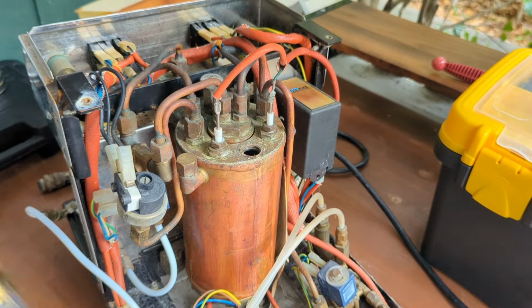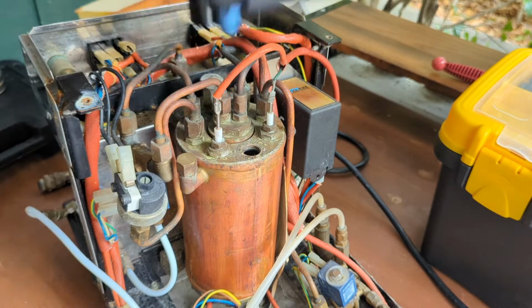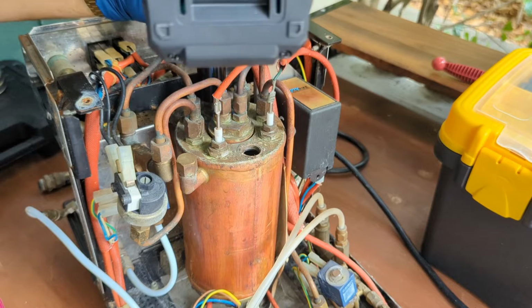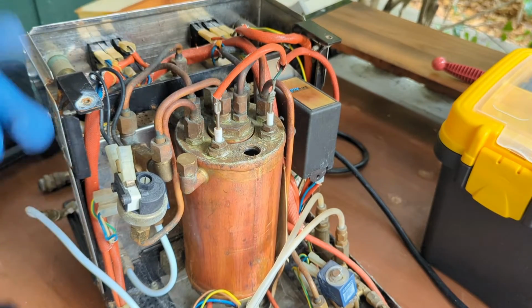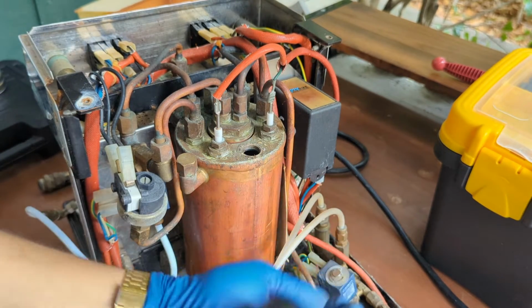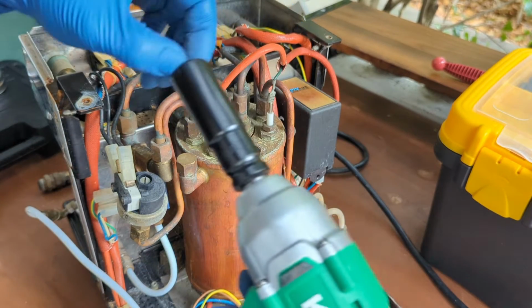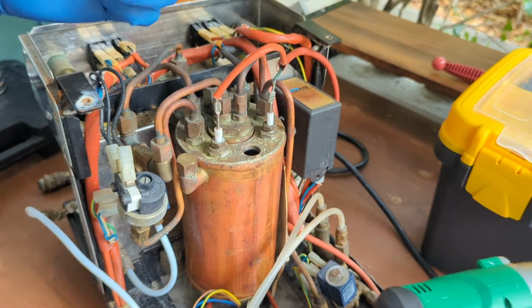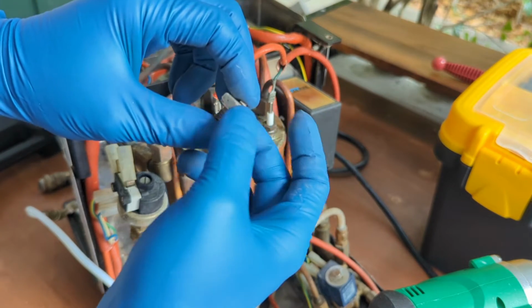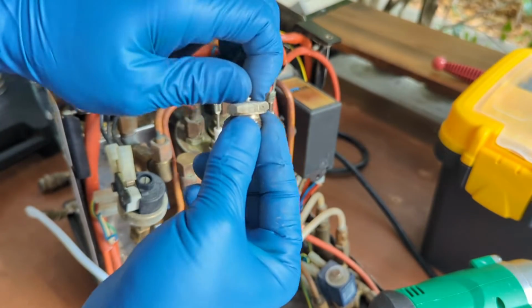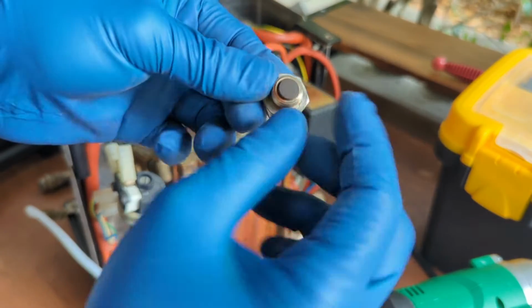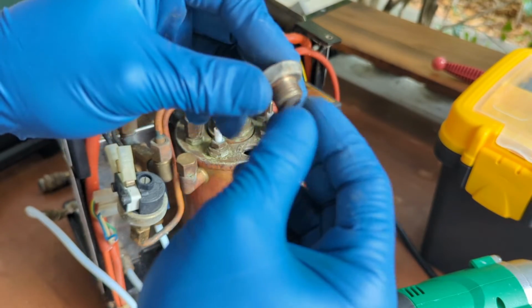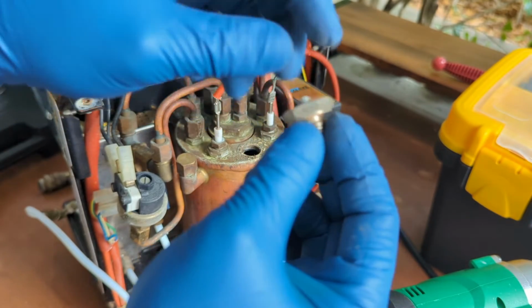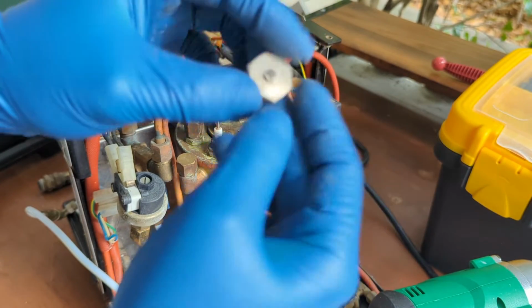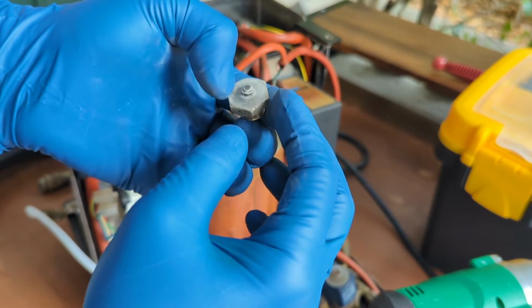Perfect. We're going to be removing the vacuum release valve. There you go. This one, we can probably save it, especially because I don't have this kind of style of vacuum release valve. I'm going to clean these very well, soak them in citric acid, and then replace the O-ring that is inside the valve. We have to remove this and then soak this.